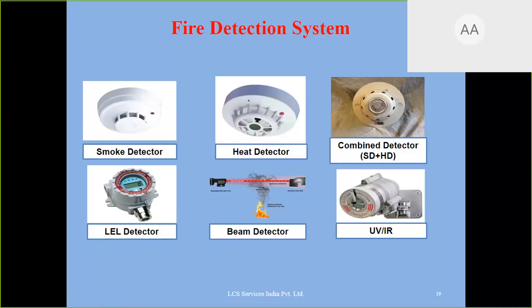Whether you use it in the bank of cylinders, or in the canteen, or in the pantry, we should have the LEL detector. Now you will ask why an LEL detector is not installed at home. We are using LPG, everybody is using LPG. Because the domestic cylinder is different from the industrial cylinder. In industries, we cannot use a domestic cylinder. We can use only an industrial cylinder.